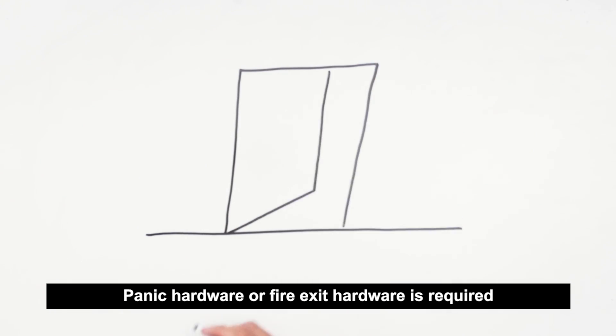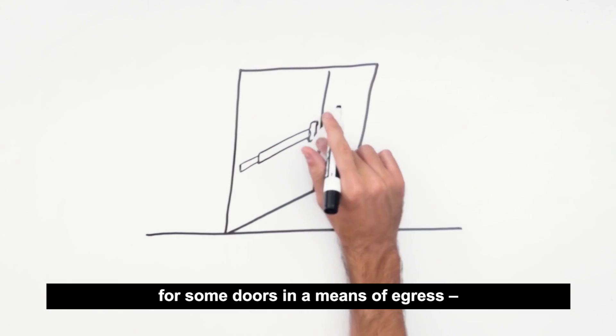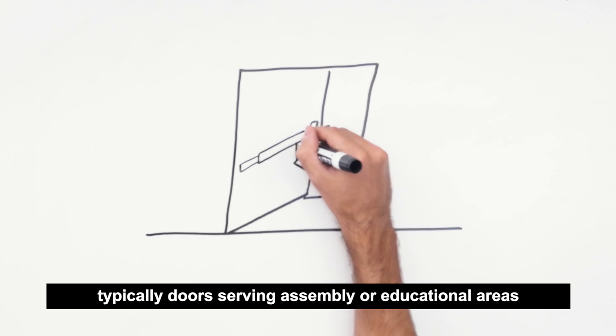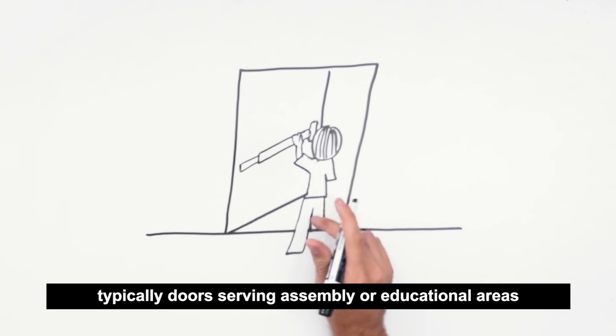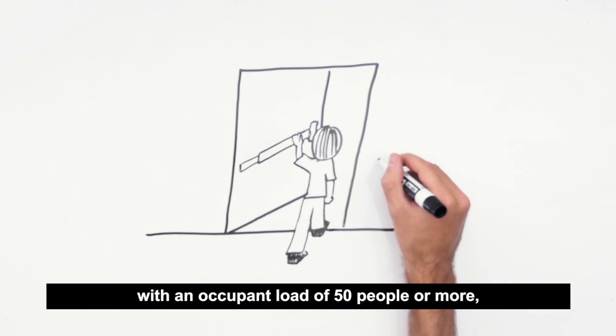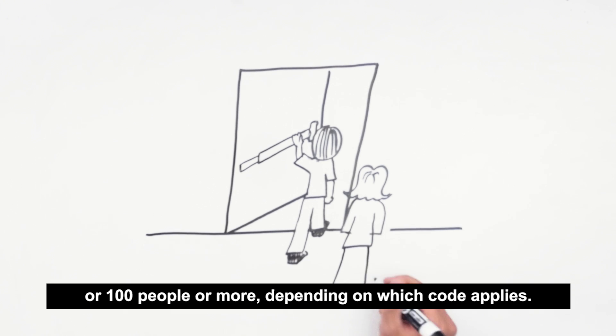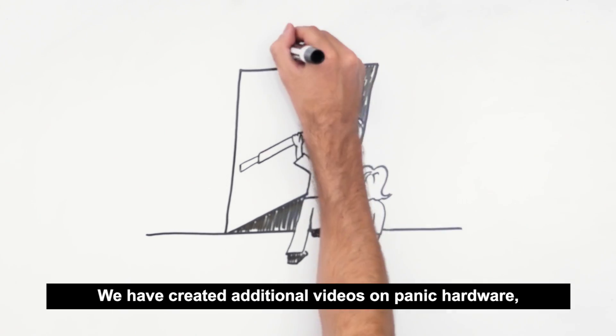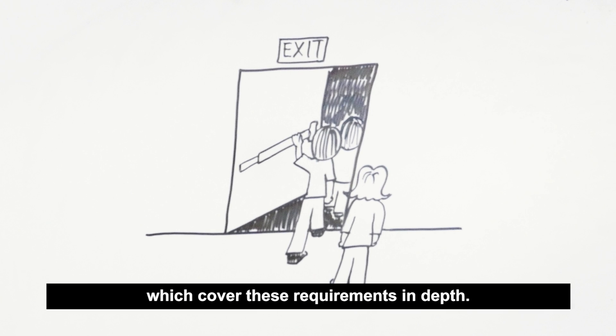Panic hardware or fire exit hardware is required for some doors in a means of egress. Typically doors serving assembly or educational areas with an occupant load of 50 people or more, or 100 people or more, depending on which code applies. We have created additional videos on panic hardware which cover these requirements in depth.